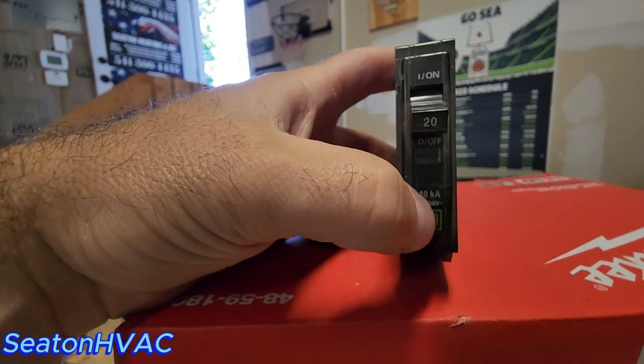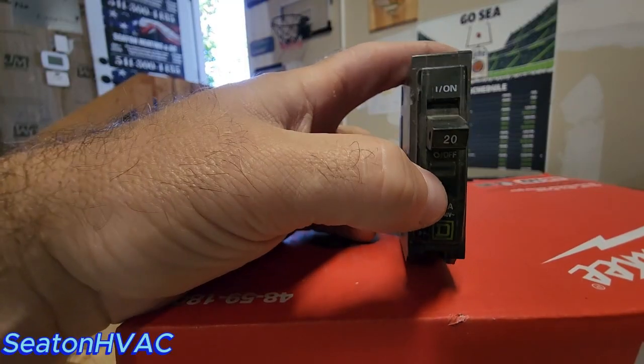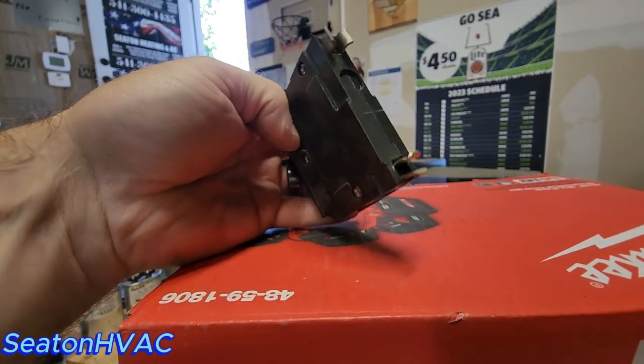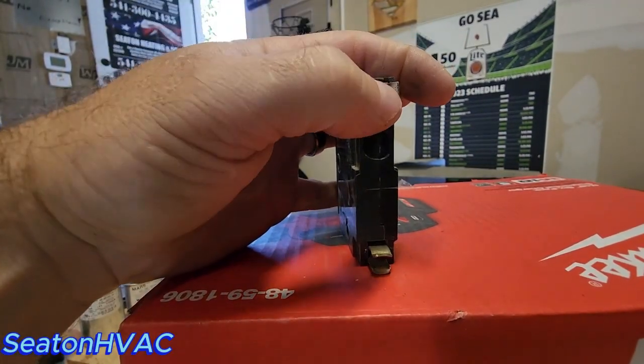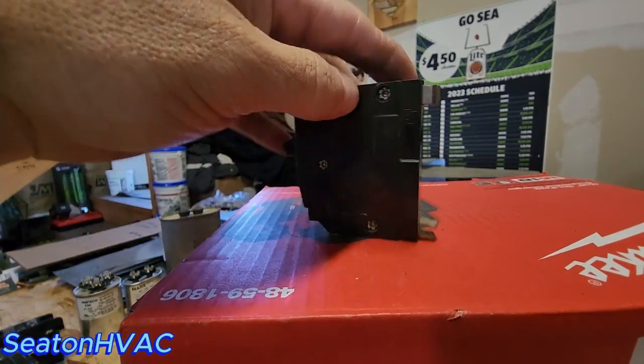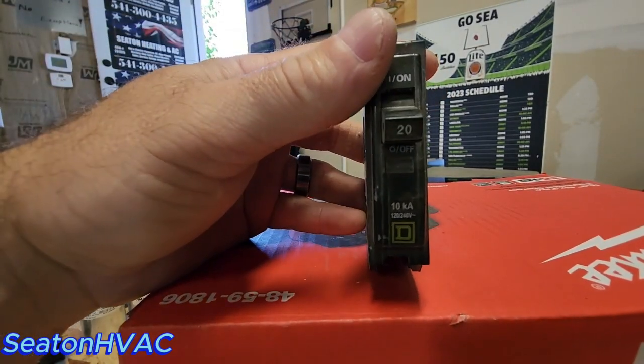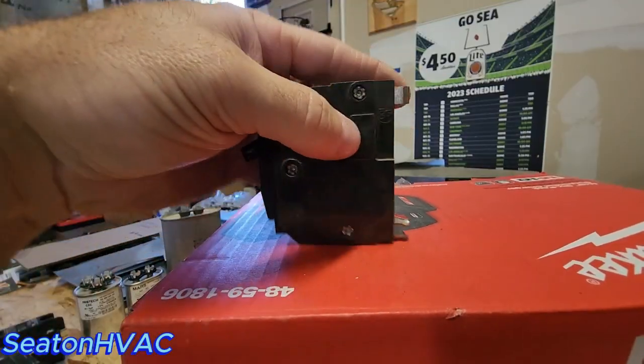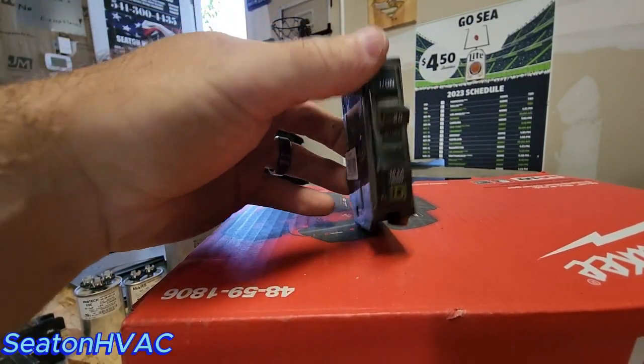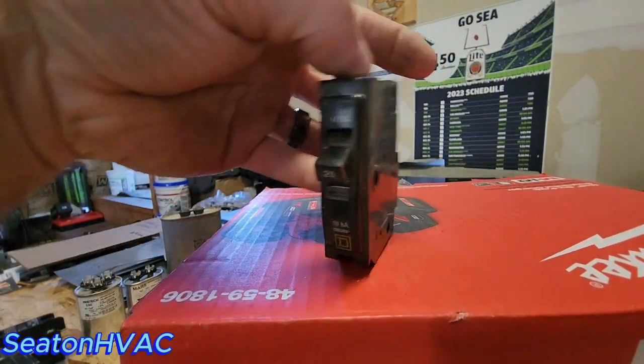This is your standard single pole 120 volt breaker. It's another Square D one. It's got the weird clips on it. This one's energized. This one's not. This just mounts it on the bus bar. 20 amp. So it's just 120 volts in, 120 volts out. And again, it'll have some fine print with its ratings on it.